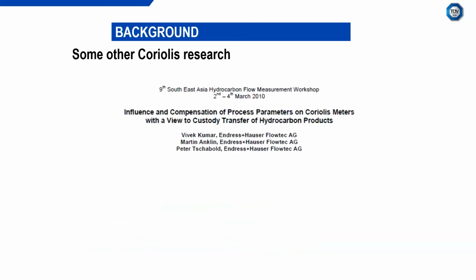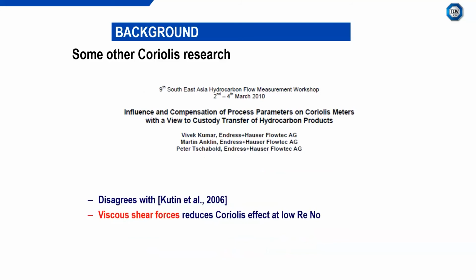There was another paper from Endress+Hauser back in 2010. They disagreed slightly with that previous paper, and they say that while it is velocity profile effects, one of the other dominating factors is viscous shear forces. These viscous shear forces from elevated viscosity fluids actually reduce the Coriolis effect at low Reynolds number. So they cause a dampening of the Coriolis forces. These viscous shear forces act in the opposing direction to Coriolis. The Coriolis force is the twisting of the tube. They're saying high viscosity fluids dampen that out and cause an underread. And this is in direct relation with Reynolds number. So the Coriolis force is dissipated in the secondary circulation. The secondary circulation of the Coriolis force is dampened by these viscous shear forces.